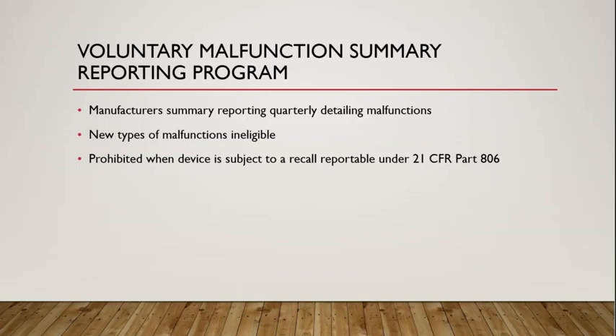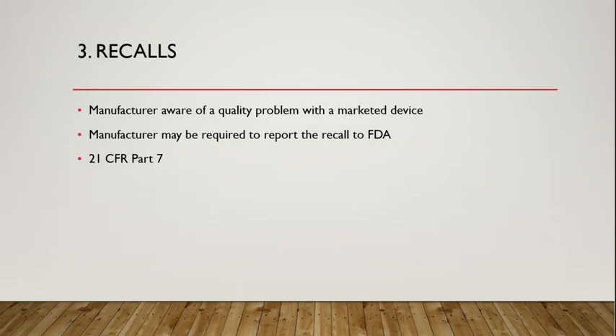Now let's close with one of the most popular and well-known features of the FDA, and that's recalls. When the truth be known, most of the recalls are self-imposed by manufacturers, and that will happen when a manufacturer becomes aware of a quality problem with a marketed device. They'll probably learn about it from a sales report or a consumer complaint, but the manufacturer will, if it's appropriate, voluntarily recall the device or the drug or whatever it is. And it may be required to report the recall to the FDA. And I put here the federal rule citation for you.